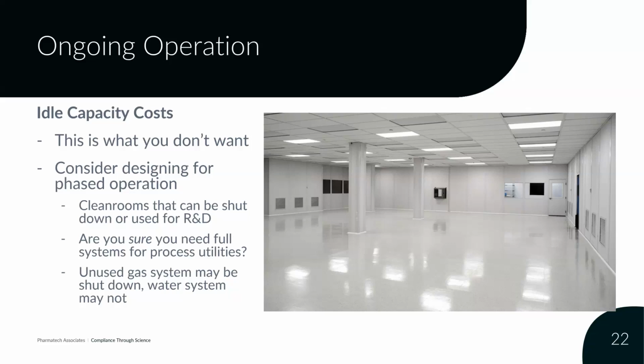An unused gas system, if you build these systems and then you wind up not using them, you can shut them down and just let them sit there and not do the routine monitoring that you would need to do if you were using them. You can just shut her down, get some little bottles of gas and use those for now. However, if you put in an RODI system, you can't shut that down and restart it without a whole lot of effort, without drastic amounts of effort and money, because you have to be able to assure the cleanliness of that water. And when you stop a water system, as most of us or all of us know, bad things happen. You're going to get all kinds of funny little things growing in the corners.